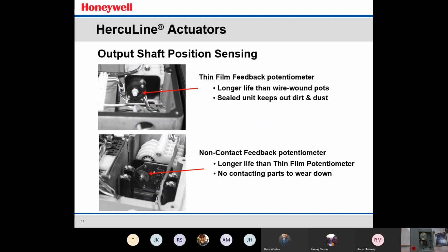This is the inside workings of a Herculine 2000 actuator, and this is basically showing the thin film pot that's available in the 2000 series, and also the non-contact feedback potentiometer. So it looks a little bit different. The thin film pot is encased in a nice plastic cover here so that it's free from getting dust and debris on the slide of the film pot, because if you do that, it becomes very erratic. And then the non-contact sensor, again, non-contacting, provides a linear feedback to your control system.